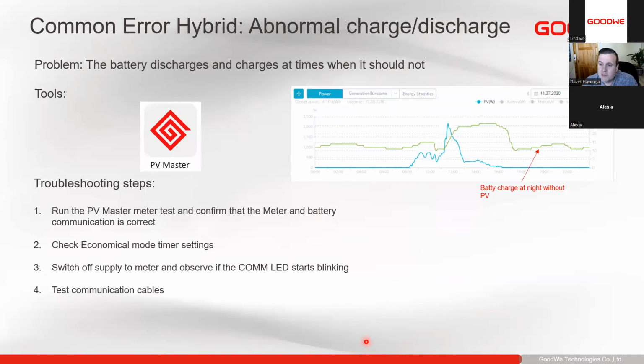Next, we have abnormal charge and discharge of the batteries. So depending on the settings, as you'll see, charging at night, things like that. So we can run PV Master and do the meter test to see whether everything is correct. We can check the economical mode time settings. So if we have set charge and discharge times, that can also explain the reason why we're charging and discharging at strange times. Switch off the supply to the smart meter and observe the COM LED on the inverter will start to blink for some of the inverters. And you can also test the communication cables.